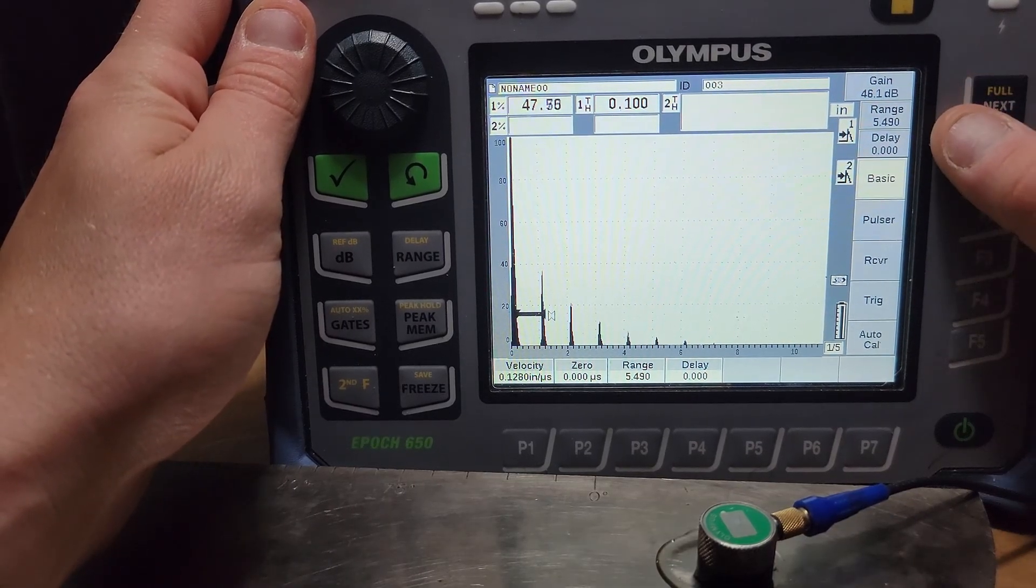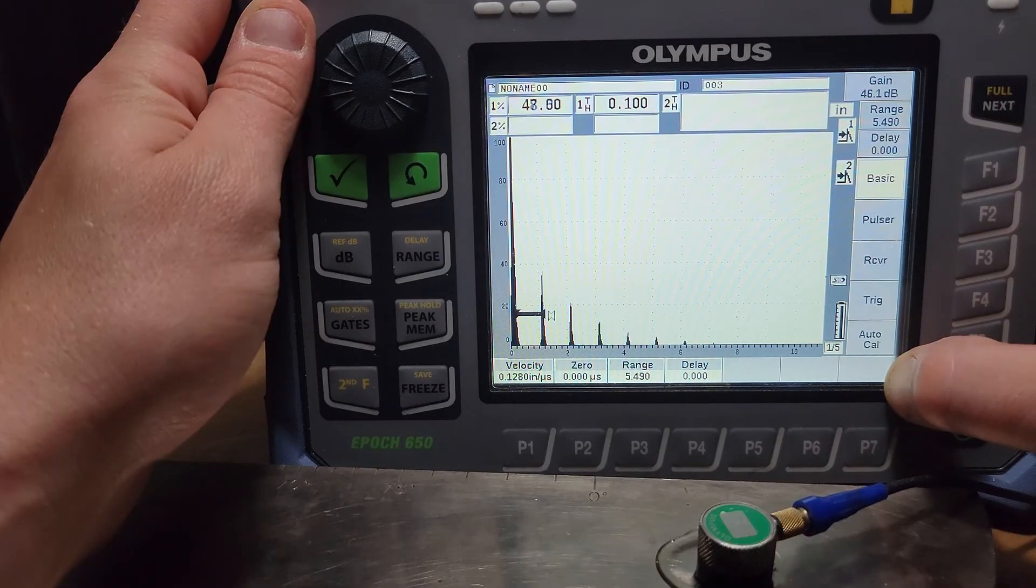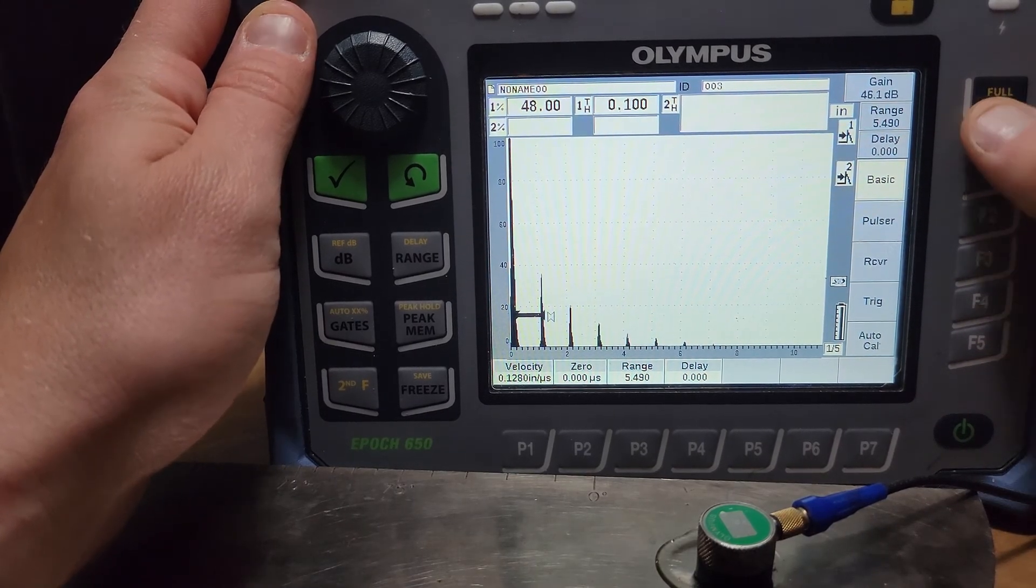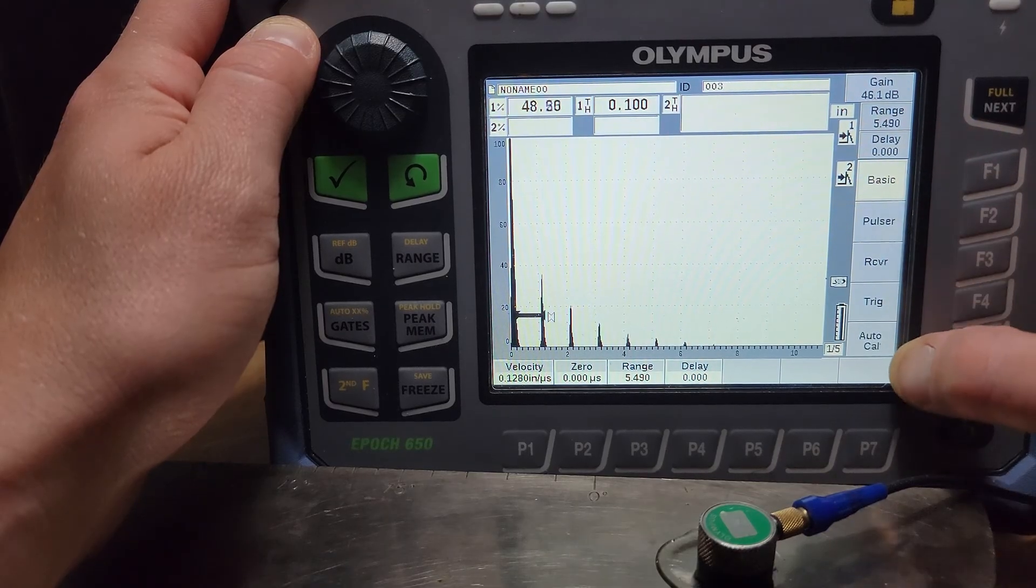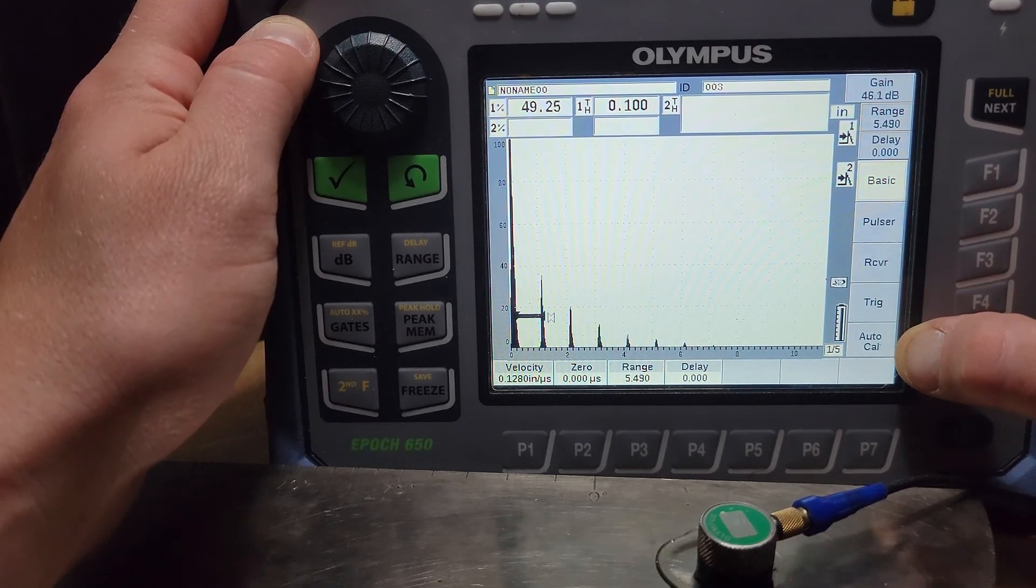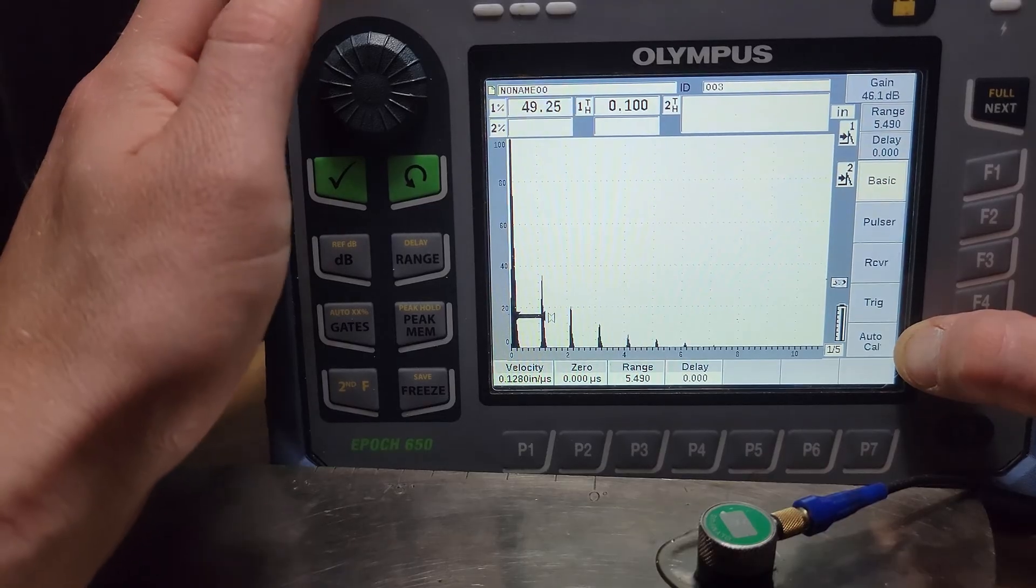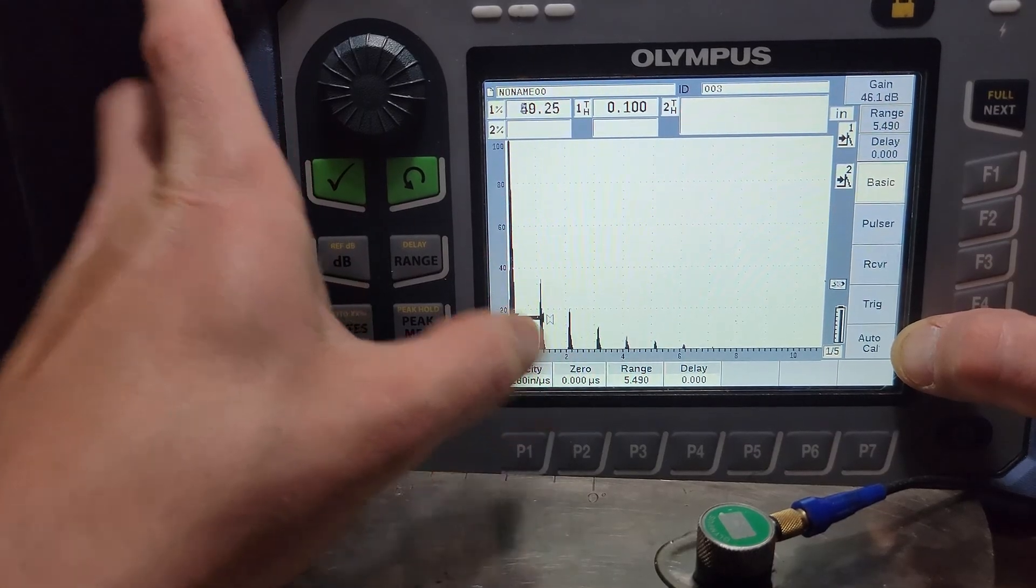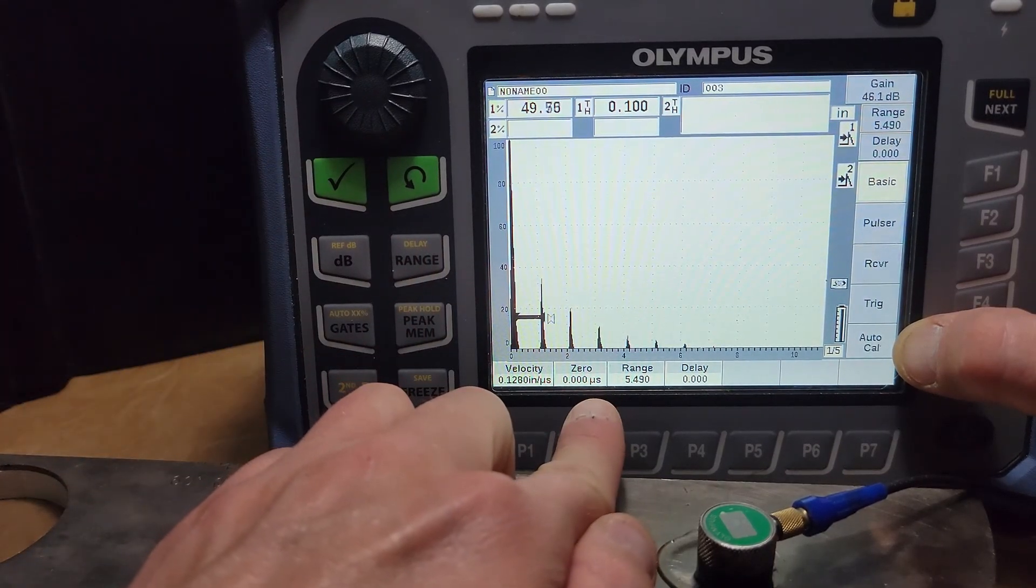So first things first, let's look at all the menus that we have possible to us. There's I believe five of these little subset menus here that you can cycle through with this next button here. We've got what I like to call this the basic menu where this is just your straight up UT settings right where you're going to have velocity, probe delay or zero offset.